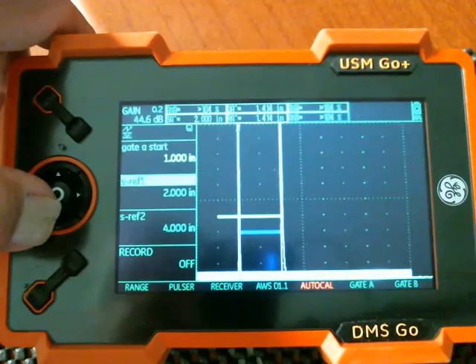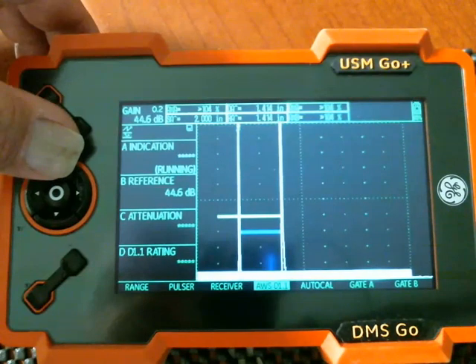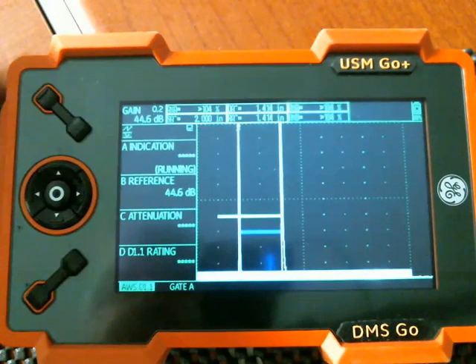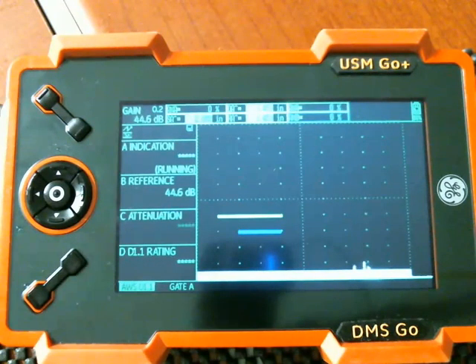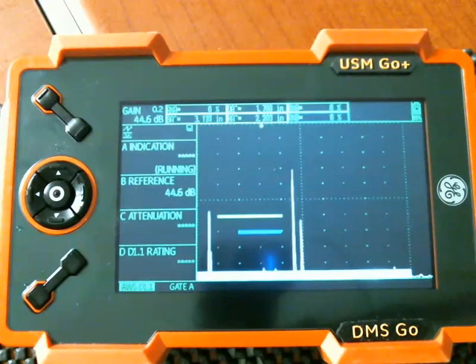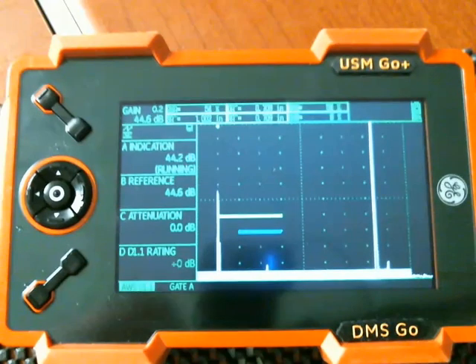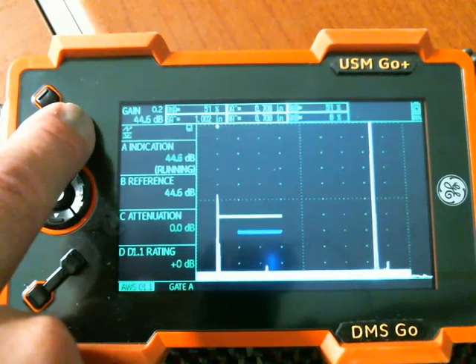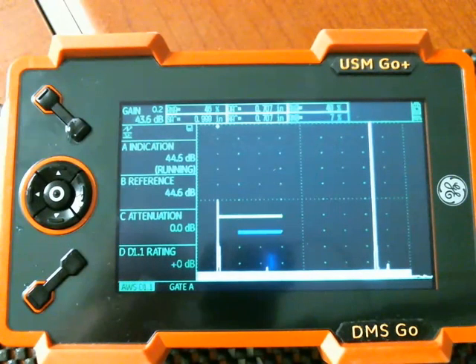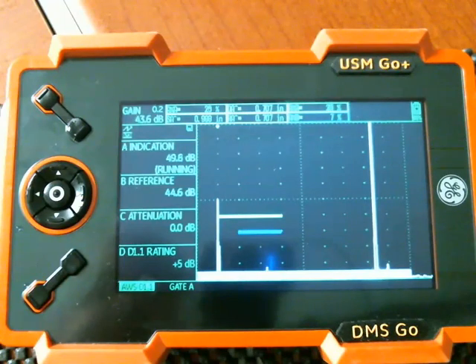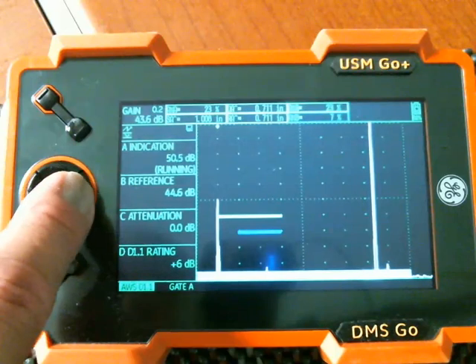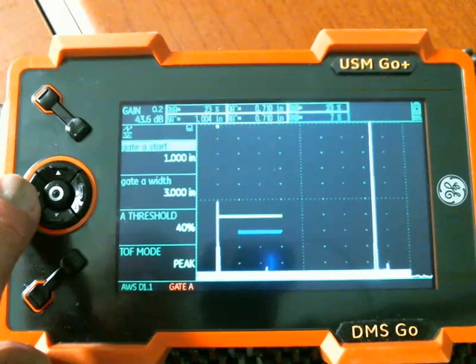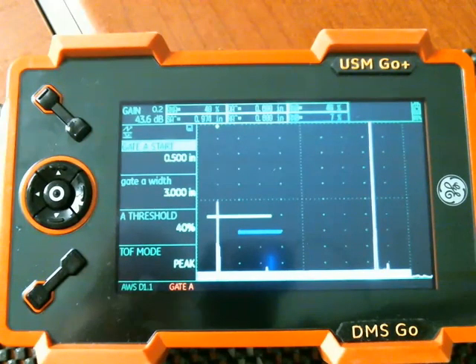And now we're going to go back down. We're going to go to the AWS menu. We're going to go up one to select the AWS menu. And I'm going to come over here and I'm going to select a hole on my other block. A side drilled hole that I want to use for a reference. And I'm going to peak up on that. Now I need to adjust my gain to give me about a 50% echo. The reference echo when you're setting this up needs to be 50% amplitude plus or minus 5%. So anywhere between 45% and 55%. So if I go to my gate A, I want to get gate A right over top of it. So gate A is now measuring that.